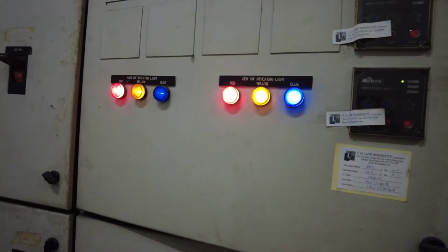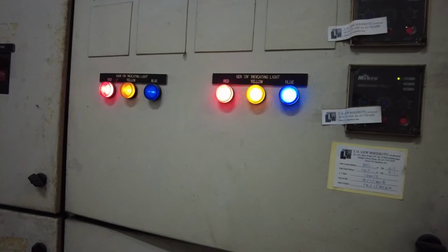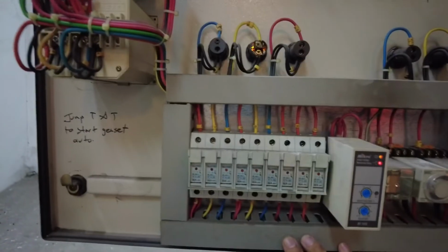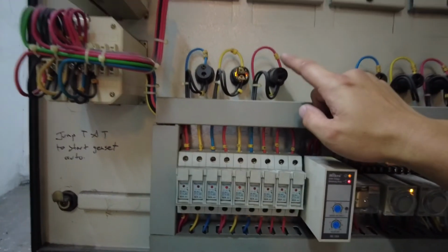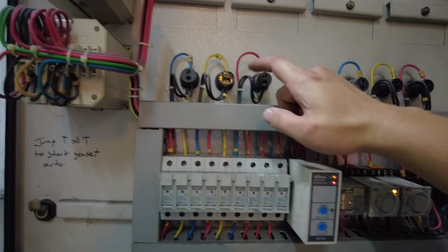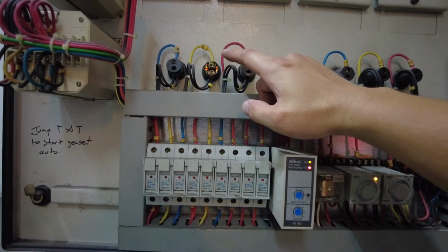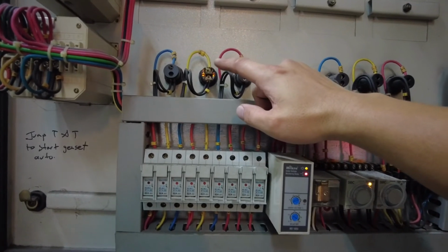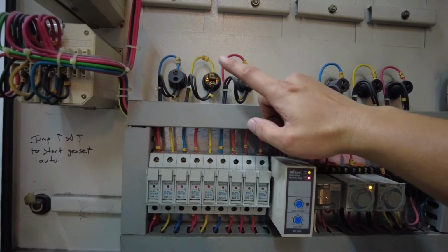And then here, you can witness the genset supply reaching here, as though it's ready to do the changeover. From this indicator light, you can use a voltmeter to check the voltage 240, 415, and also check the frequency. This also confirms there's no tripping at the AMF panel. The genset supply reaches here.